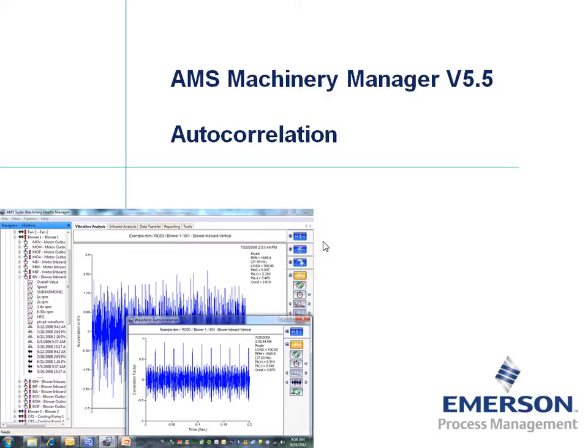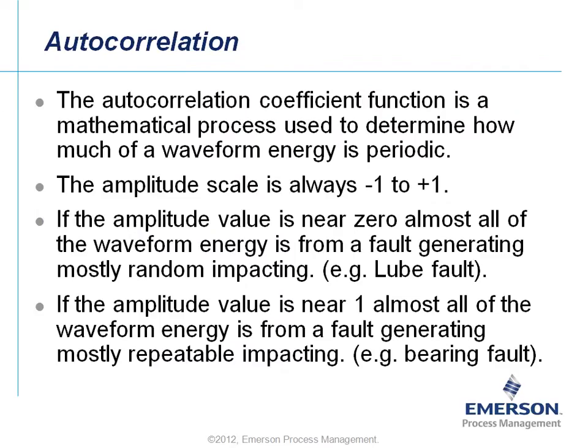This tutorial covers the autocorrelation feature inside AMS Machinery Manager version 5.5 or higher. The autocorrelation coefficient function is a mathematical process used to determine how much of a waveform's energy is periodic. The amplitude scale is always from minus 1 to plus 1. If the amplitude value is near 0, almost all of the waveform energy is from a fault generating mostly random impacting — for example, a lubrication fault.